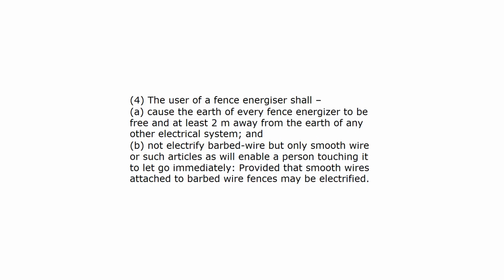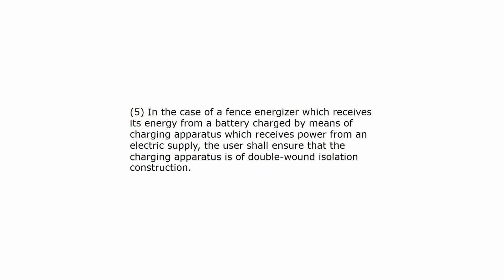The user of a fence energizer shall cause (a) the earth of every fence energizer to be free and at least 2 meters away from the earth of any other electrical system, and (b) not electrify barbed wire but only smooth wire or such articles as will enable a person touching it to let go immediately, provided that smooth wires attached to barbed wire fences may be electrified. In the case of a fence energizer which receives its energy from a battery charged by means of a charging apparatus which receives power from an electric supply, the user shall ensure that the charging apparatus is of double wound isolation construction.